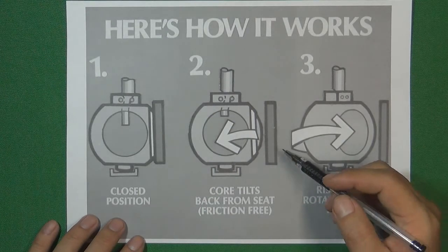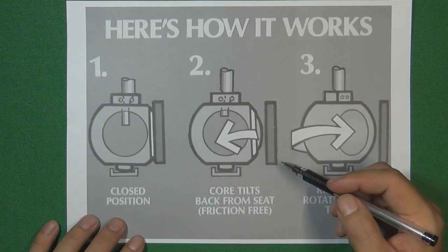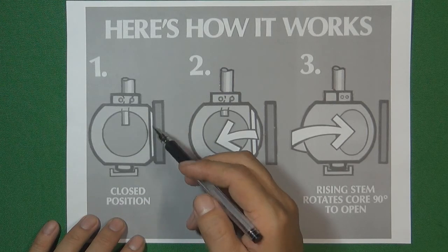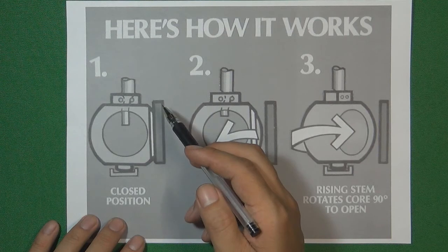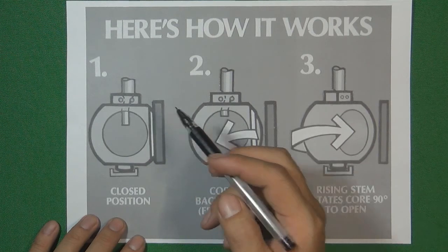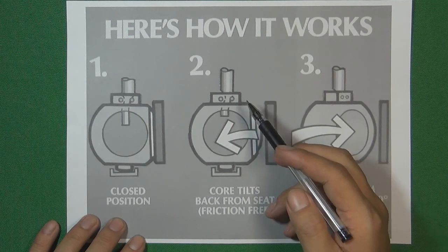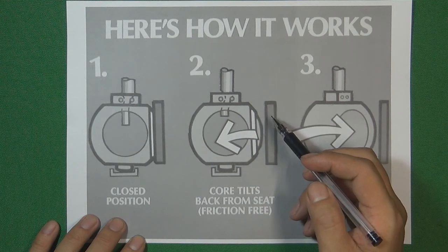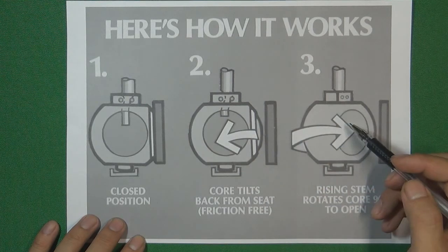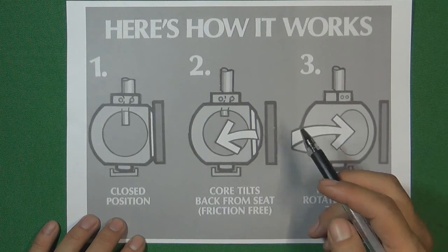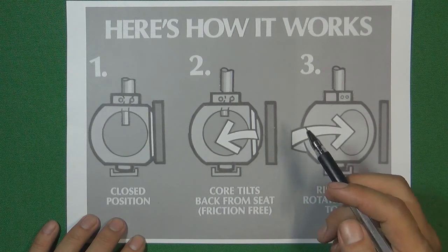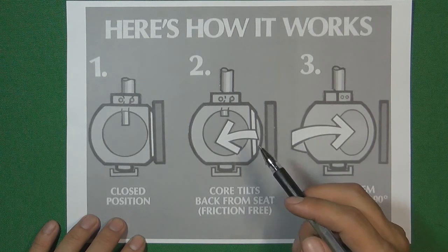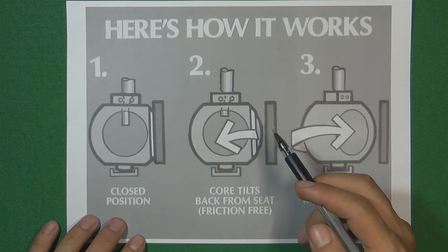This illustration explains how the orbit ball valve opens. First, in the closed position, the ball sealing face is touching the valve seat sealing face. Then we operate the valve stem to open the ball valve: the first movement is the ball leaving the valve seat, and then the ball turns. So this kind of design is very special — this kind of ball valve can work in very critical flow control systems. When we open it, the ball sealing face will never touch the valve seat sealing face.